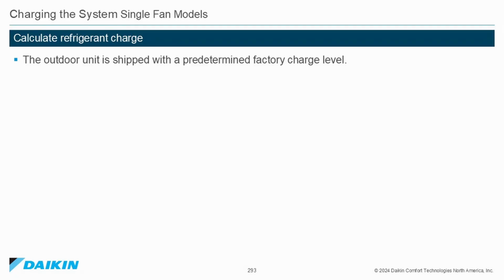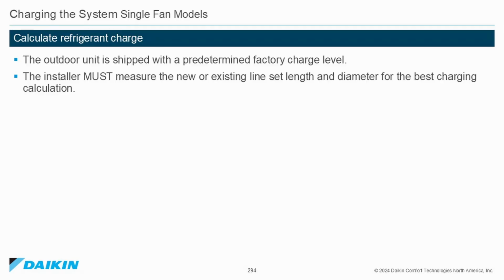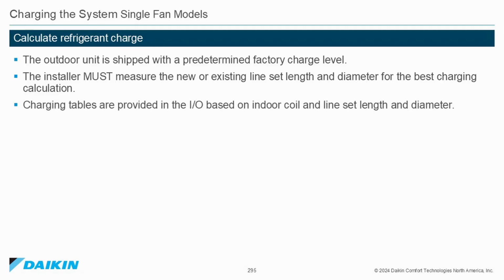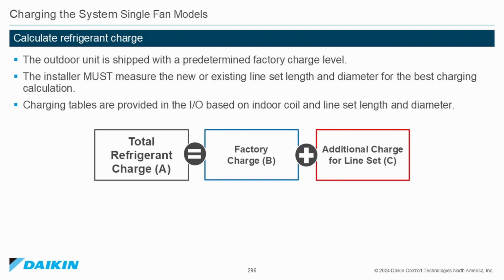Charging the system, single fan models. Calculate refrigerant charge. The outdoor unit is shipped with a predetermined factory charge level. The installer must measure the new or existing line set length and diameter for the best charging calculation. Charging tables are provided in the installation operation manual based on indoor coil and line set length and diameter. The total refrigerant charge, A, is equal to the factory charge, B, and the additional charge for the line set, C.